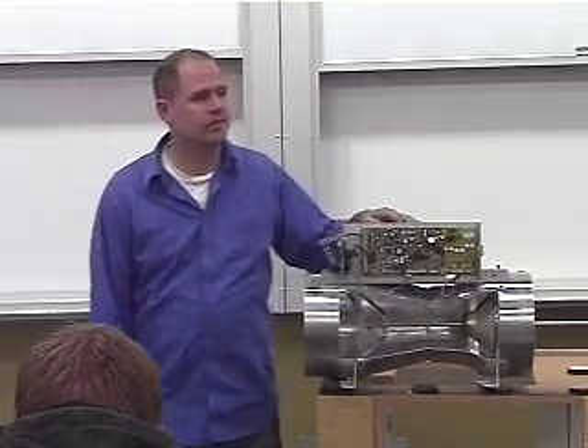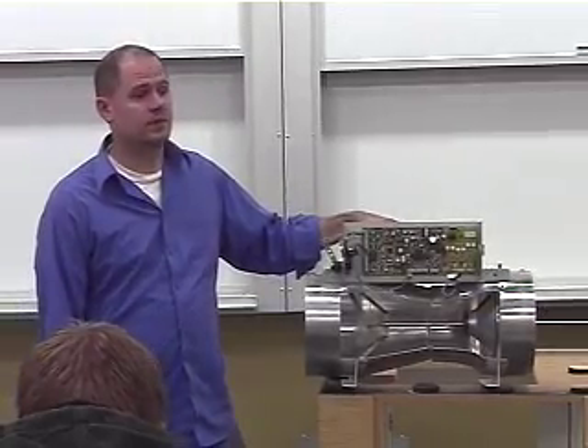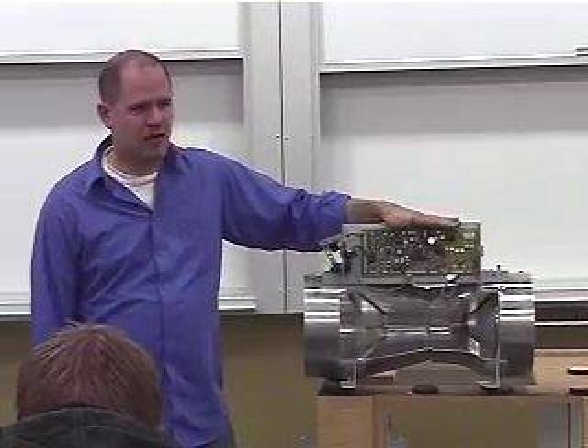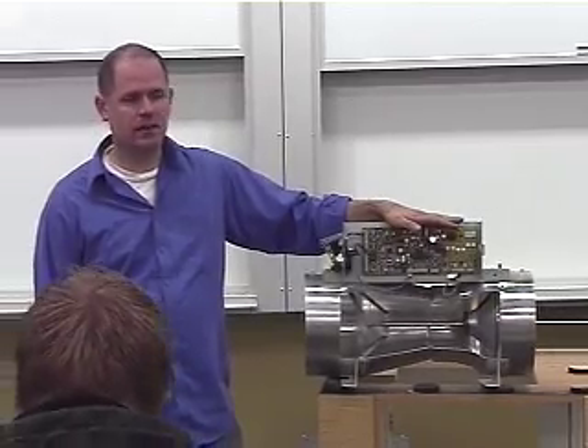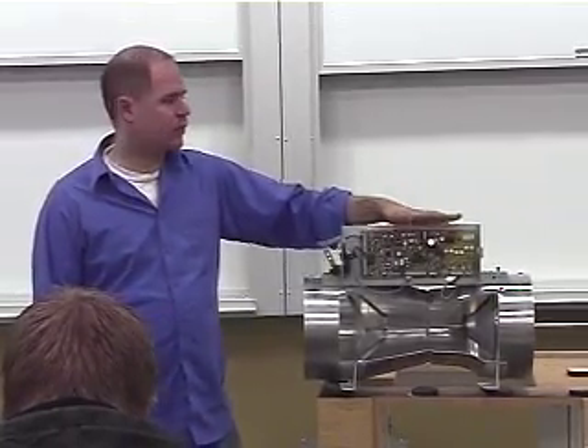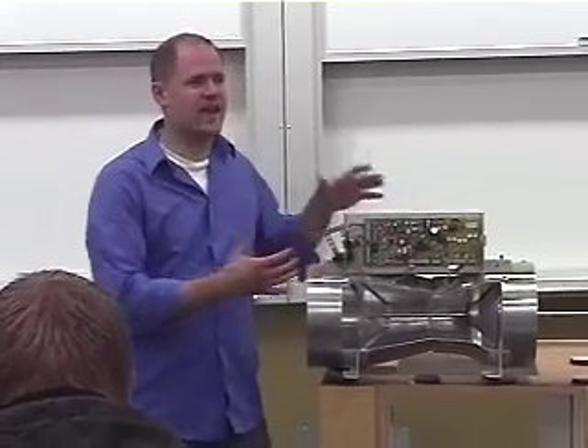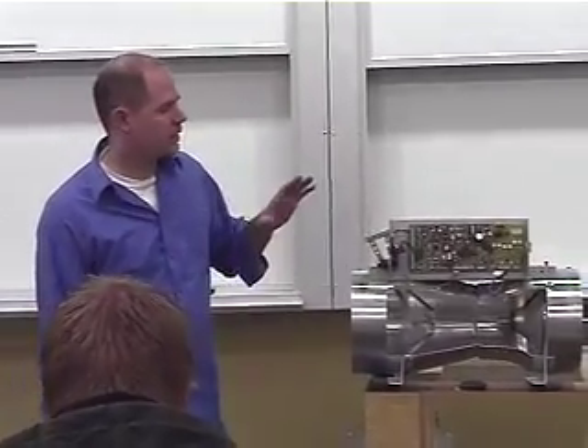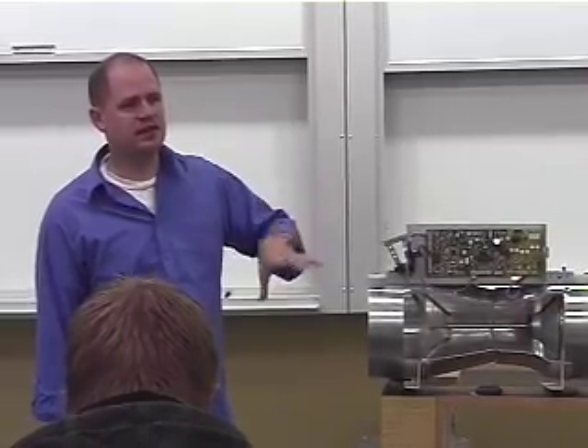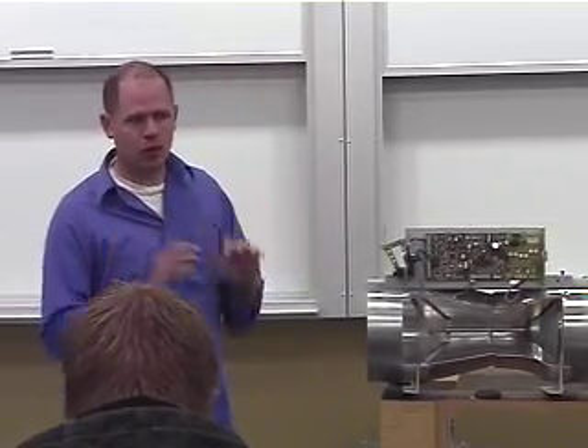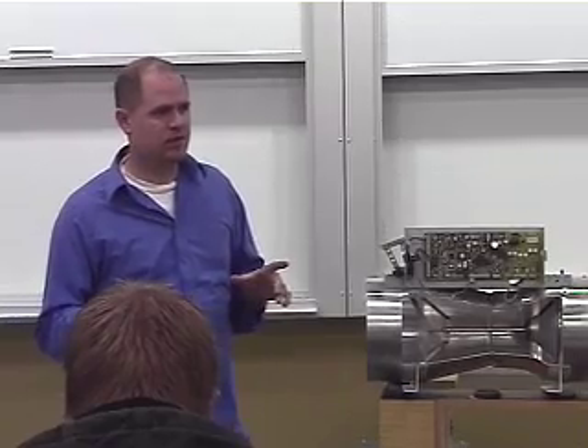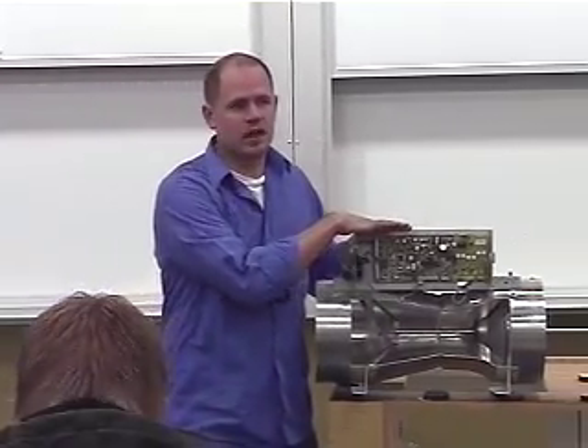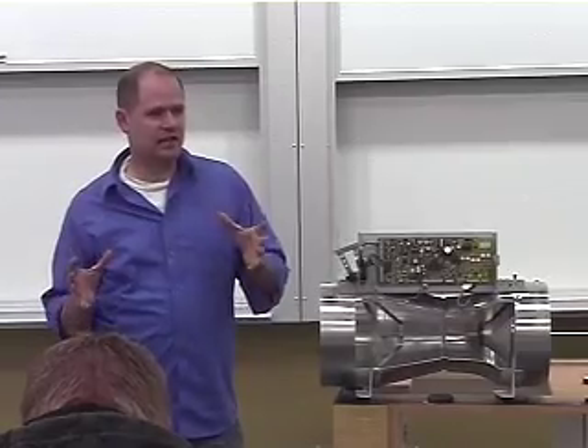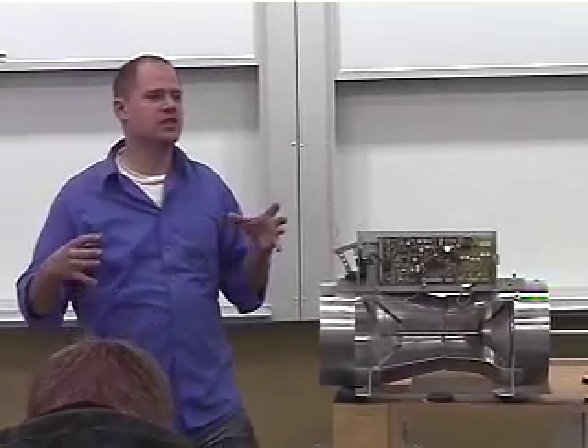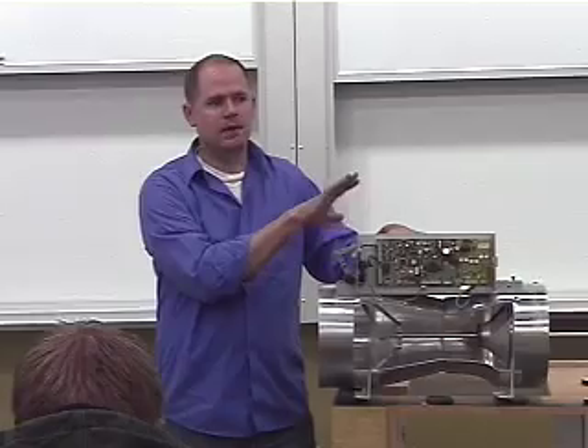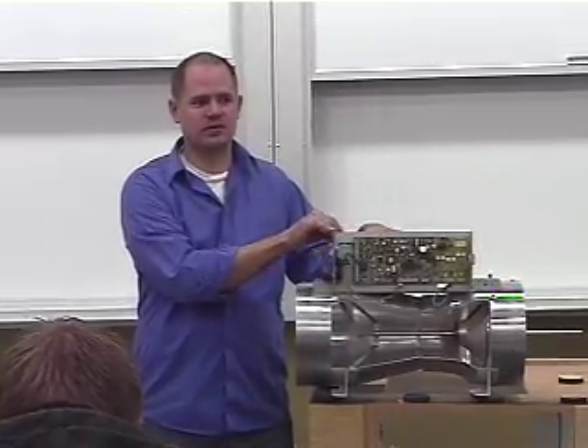Are these all 24 volt supply then? Yes. So 24 volt AC supplies power to these and the fume hood monitors. Some of the older Phoenix stuff was before they went to the LON-based circuit board and everything, when they had the analog age, they had a plus and minus 15 volt DC supply. So I don't know if you have any old Phoenix stuff around on your campus, but this building is all 24 volt AC. If you have the high-speed motors, they actually require a 100 VA transformer for each high-speed valve because of the inrush current when you power up those capacitors.